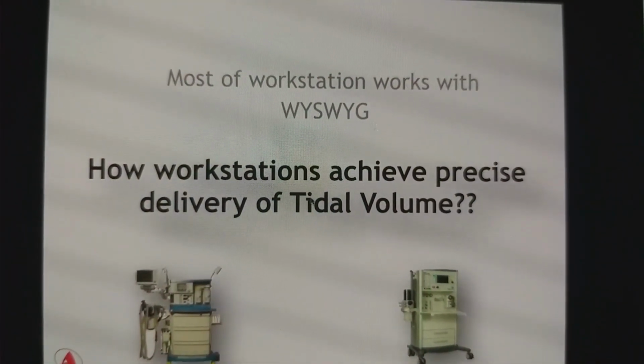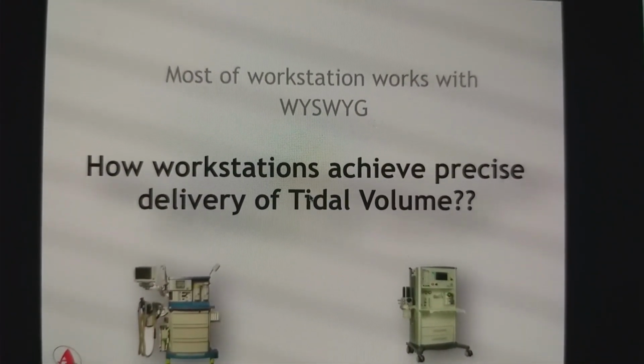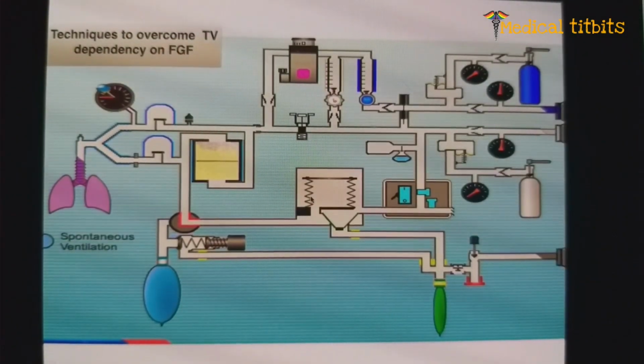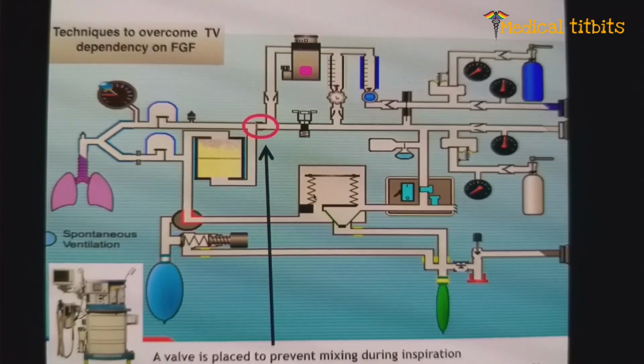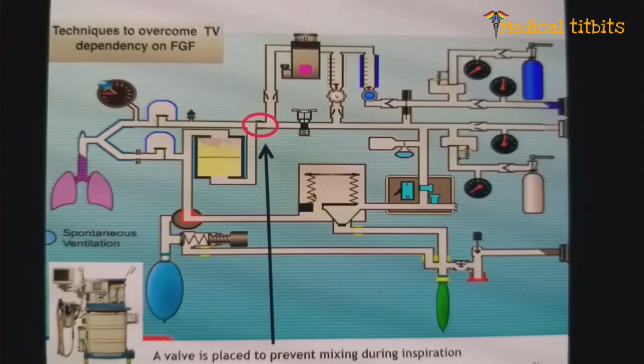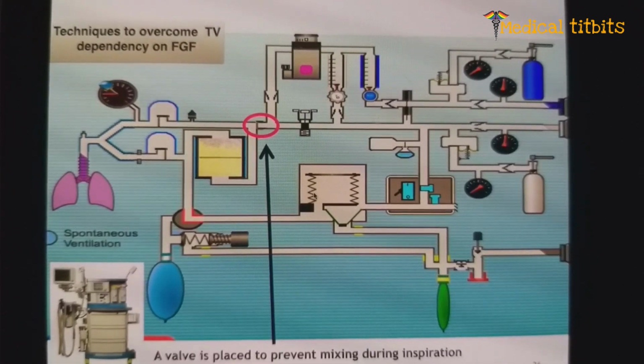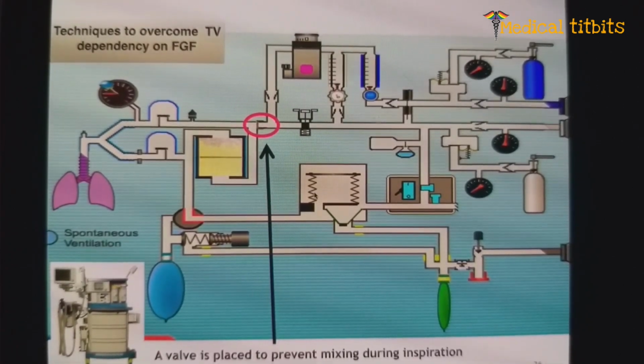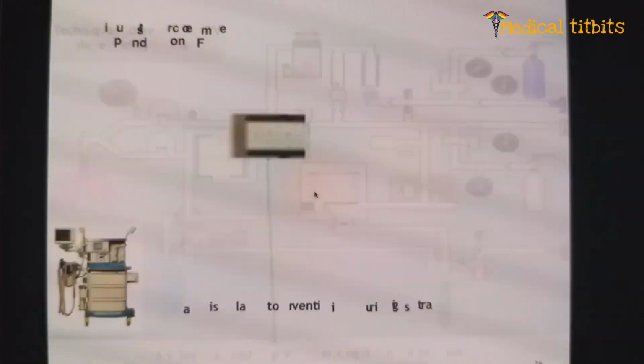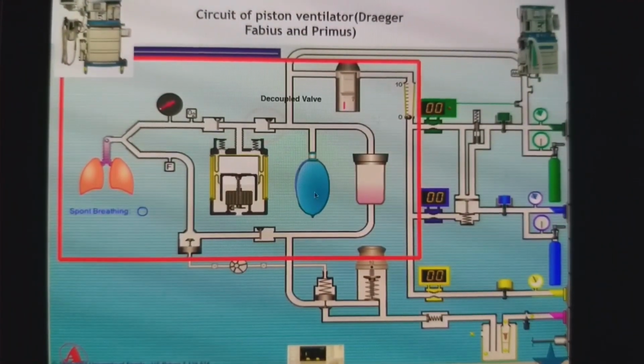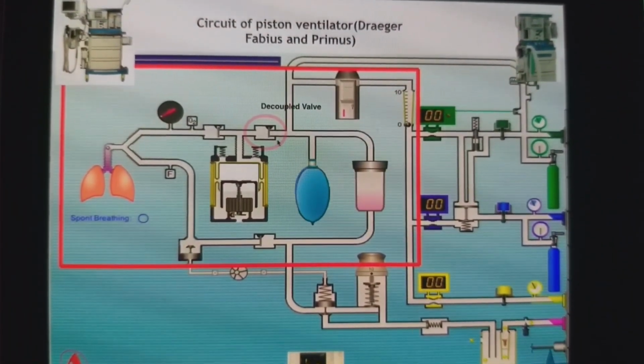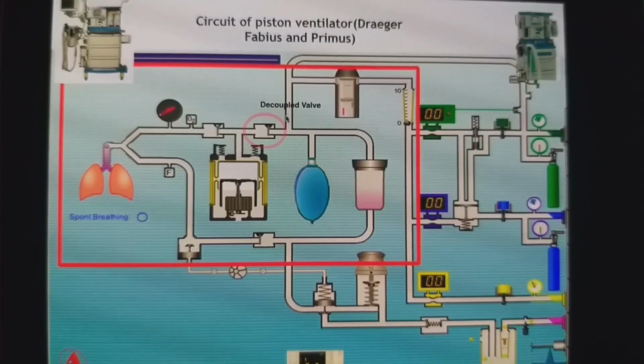Now, how does the workstation try to avoid this? How do they achieve precise delivery of tidal volume? The culprit here is this particular point. The mixing of ventilator flow and fresh gas flow is a major reason. So the solution the Draeger company has come out with is called the decoupling valve. Here they have made a one-way valve in this inspiratory line.